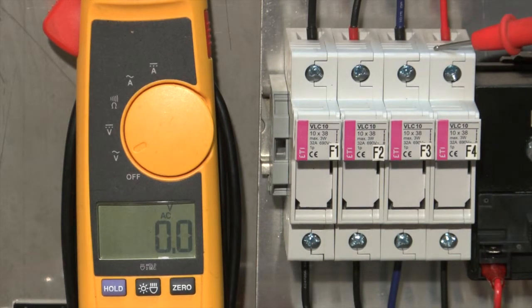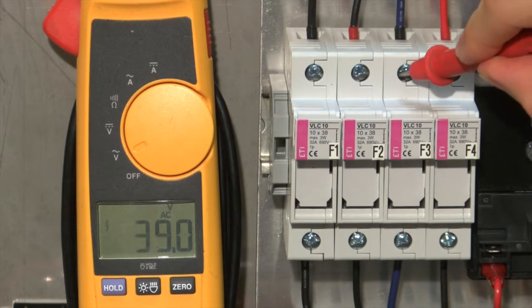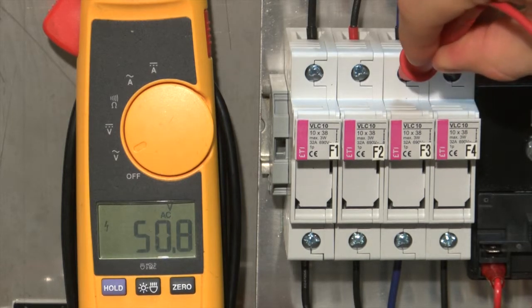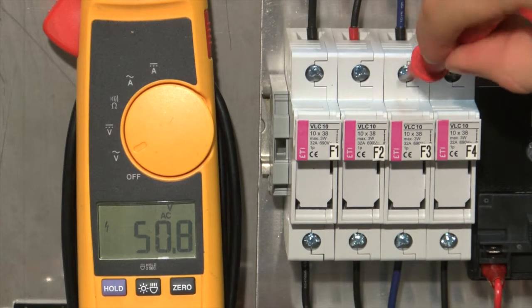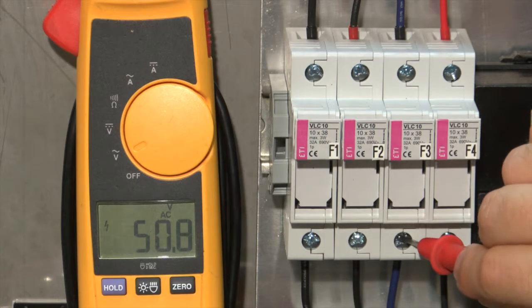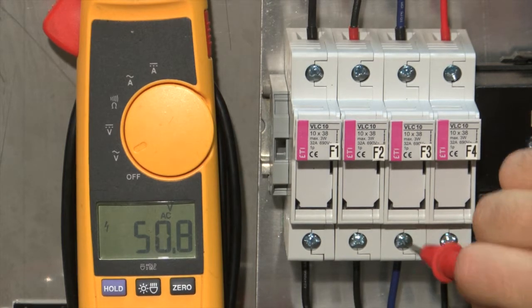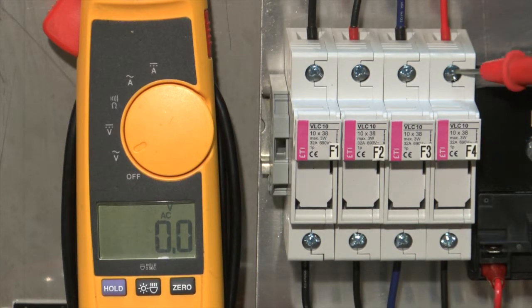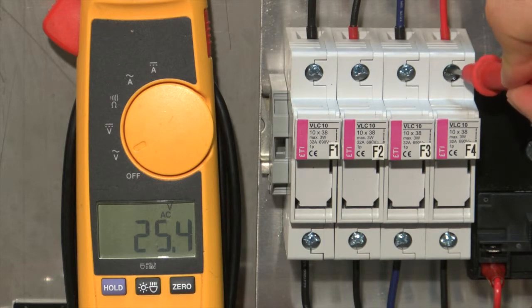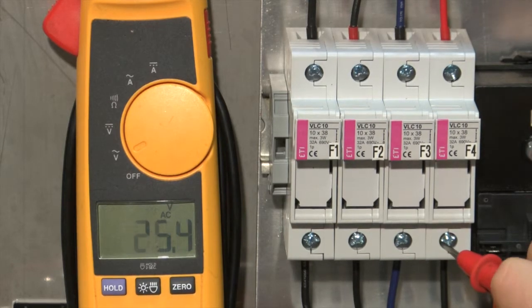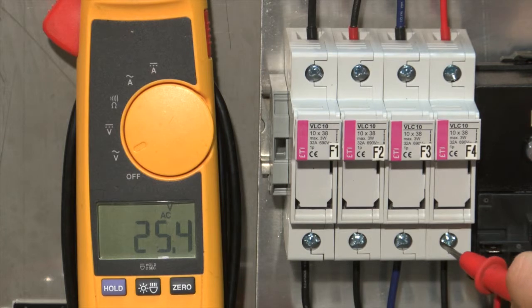When checking your secondary fuses, be sure you're using the secondary or orange tap on the transformer to get an accurate reading. In this case, we have one prong on the secondary neutral and can check the 48 volts coming in, the 48 volts going out, and on the 24 volt fuse we can see the 24 volts coming in and the 24 volts coming out.